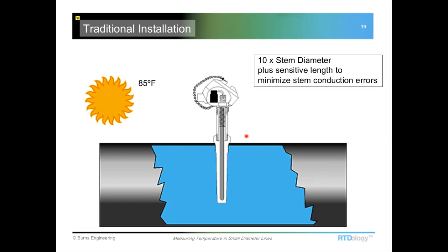And the external portions of the sensor assembly act as a bit of a radiator at that particular point. And so we're going to have heat conducting along not only the metal thermowell in the probe, but the actual lead wires in the probe. And that's going to affect the measurement if there is not sufficient immersion length into the process to overcome those errors.